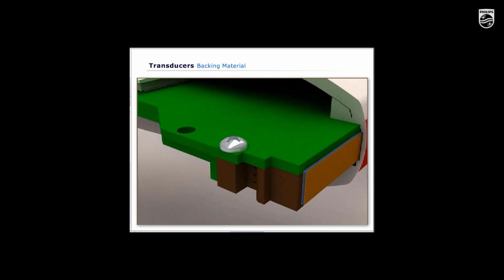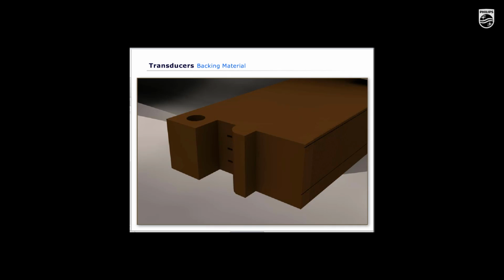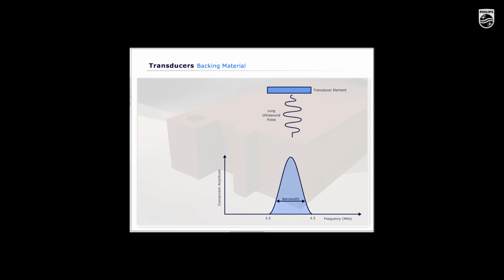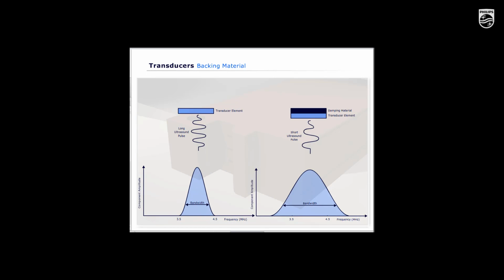The backing material is a mixture of metal powder and a plastic or epoxy. Without damping, a transducer element produces a long ultrasound pulse of many cycles. With damping, on the rear face of the transducer element, a short ultrasound pulse of a few cycles is produced. The shorter the pulse, or the fewer the number of cycles, the more frequencies present in it, or the broader the bandwidth. A shorter pulse also improves resolution. This will be explained in more detail later on during the resolution section. Typically, pulses of 2 or 3 cycles are generated with diagnostic ultrasound transducers.